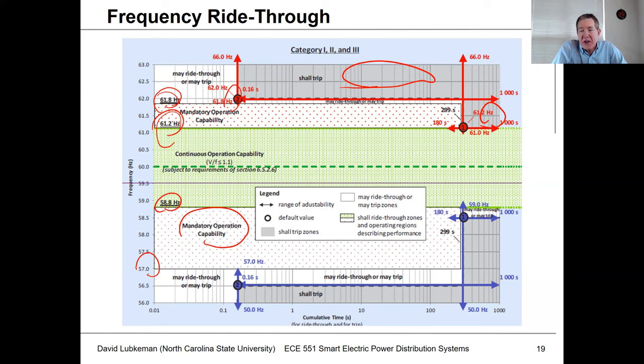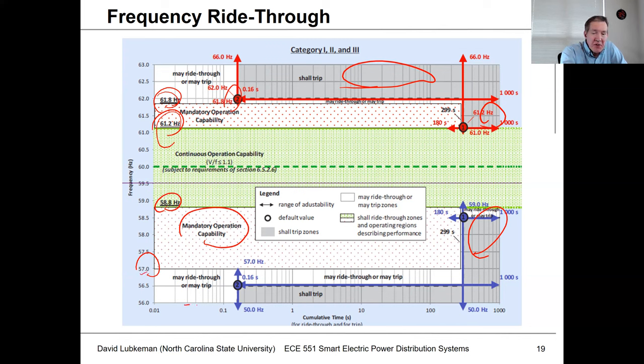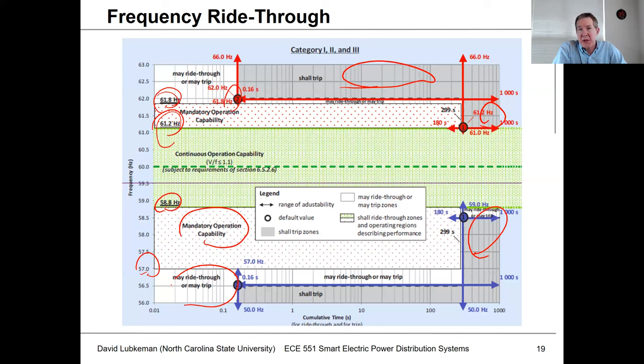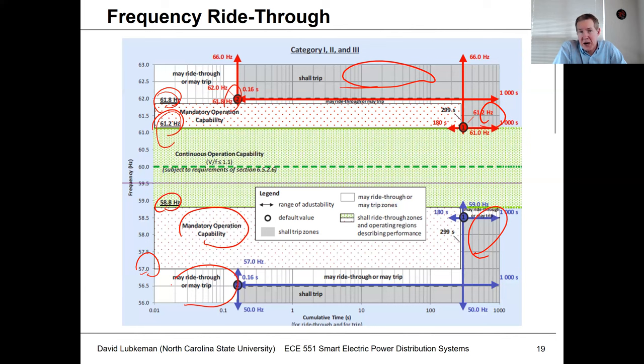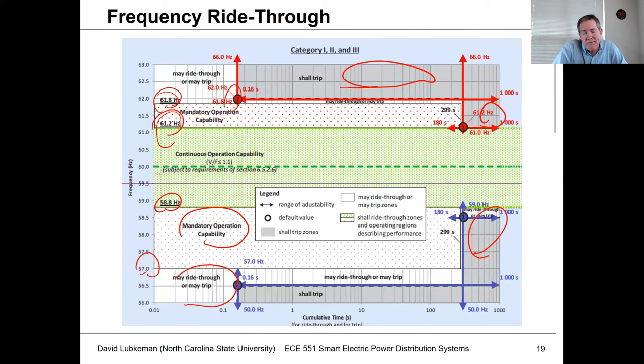Basically what it needs to do is hang in there up to a certain time. Once you get below 57 hertz, you have the option of whether you're going to ride through or trip. If you're in a large-scale grid and you get all the way down to 57 hertz, you're in big trouble. While large-scale synchronous generating units powered by steam or gas turbines can operate that low in frequency, once you get that low, everything's going to fall apart — you're probably heading into a blackout. Dropping down to 58.8 hertz could happen; it's not an uncommon event. But below 57, you're basically on your way to a blackout situation anyway.